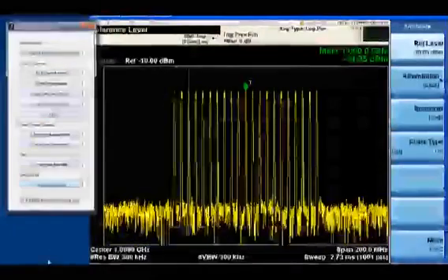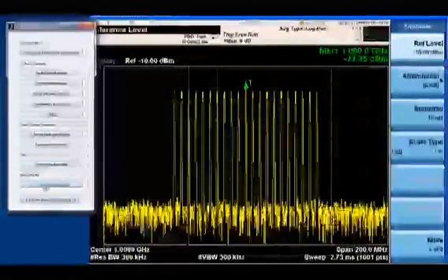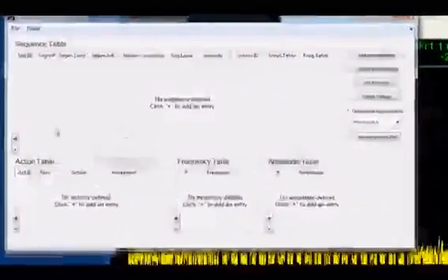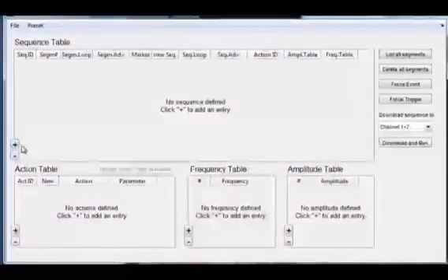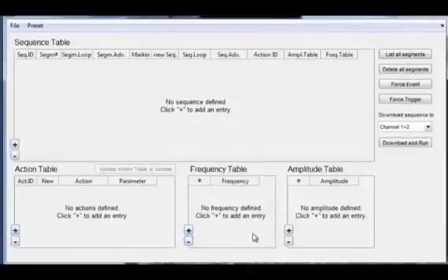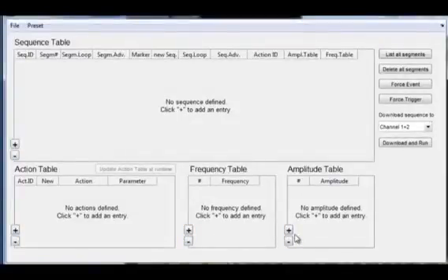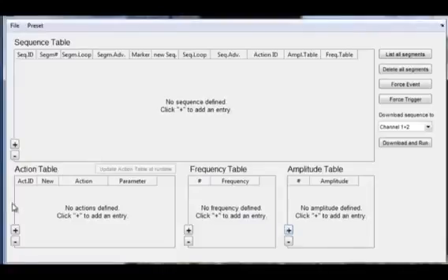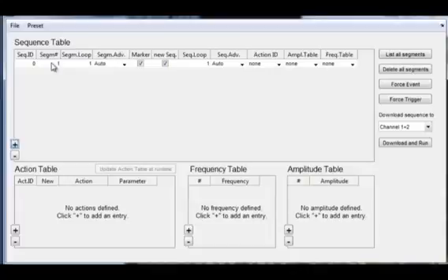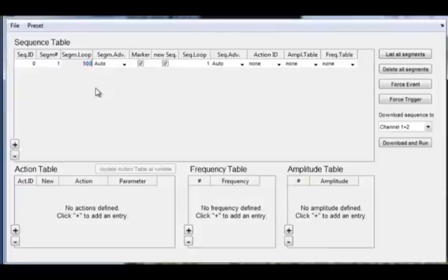Next I want to show you how we can modify the signal using the sequencer. I'm going to open up the sequencer setup here and you notice it comes up with an empty sequence. You can use these plus and minus buttons to add and remove entries into the individual tables. I'll start out with putting an entry into the sequence table. By default it comes up with playing segment number one, and I will play this segment 5,000 times so that we can see something on the spectrum analyzer.